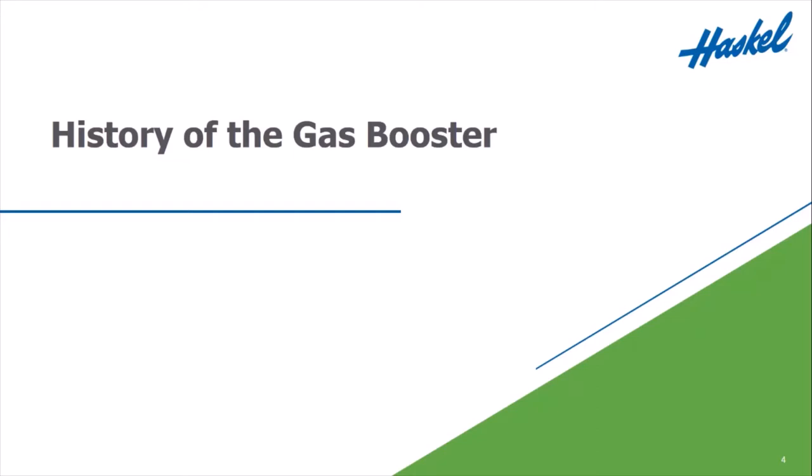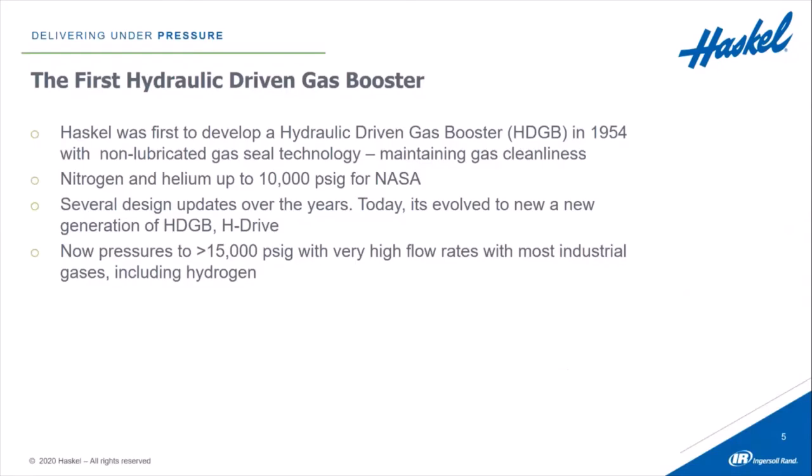Thanks, Irma. I'm very excited to be here today to talk about Haskel's latest innovation in gas booster compression technology. Before we jump into our new technology, let's give you a little history on where Haskel has been. In 1954, Haskel was the first company to develop a hydraulically driven gas booster that used a non-lubricated, dry seal in the gas section. That dry seal allowed us to maintain a much higher level of gas cleanliness than had been achieved before. These new hydraulically driven boosters were used primarily by NASA for boosting nitrogen and helium up to 10,000 PSI. Over the last several years, Haskel has had a number of design updates. The latest design is called the H-Drive, which is capable of generating pressures greater than 15,000 PSI with very high flow rates, and it can handle most industrial gases, including hydrogen.